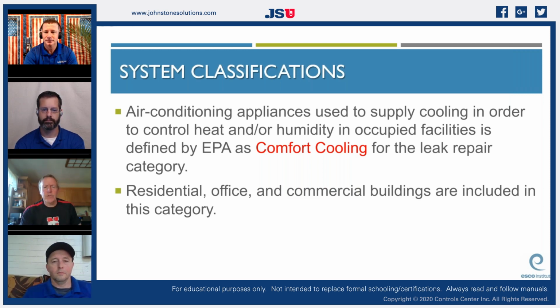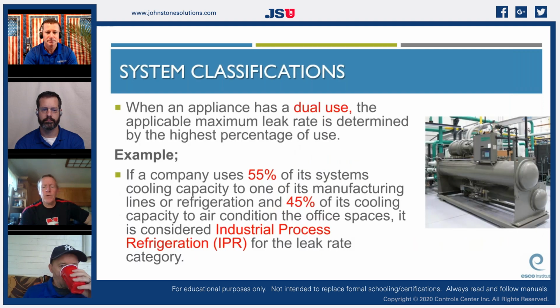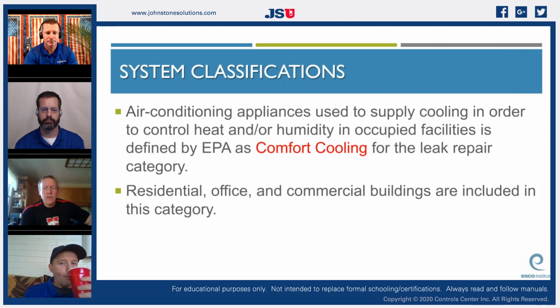Okay, the way to categorize the leak amounts you're allowed are 3 different categories. We'll go through them. It's comfort cooling, commercial refrigeration, and IPR, and we'll hit each one of them. Comfort cooling is just what it says it is. It's air conditioning. So whether it's a 2-ton unit in the backyard or it's a 25-ton unit on the roof, the difference is when they hold a certain amount of refrigerant, there are documented leak requirements. And comfort cooling is always the lowest. It's 10%. We'll cover that in detail.